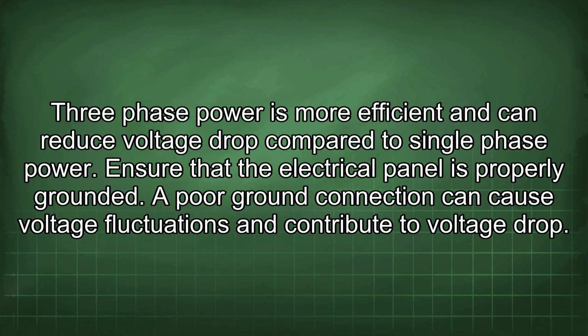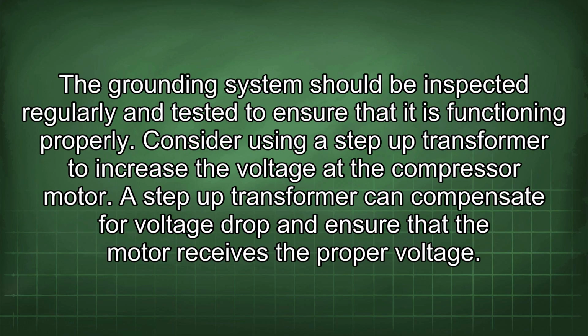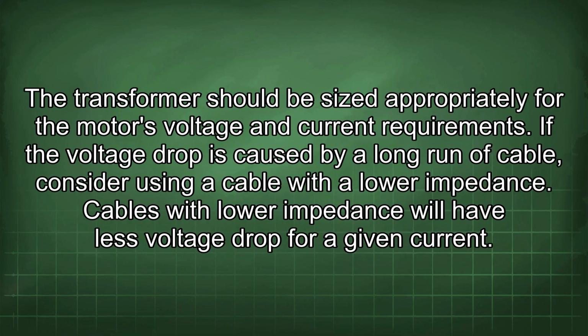Ensure that the electrical panel is properly grounded. A poor ground connection can cause voltage fluctuations and contribute to voltage drop. The grounding system should be inspected regularly and tested to ensure that it is functioning properly. Consider using a step-up transformer to increase the voltage at the compressor motor. A step-up transformer can compensate for voltage drop and ensure that the motor receives the proper voltage. The transformer should be sized appropriately for the motor's voltage and current requirements.